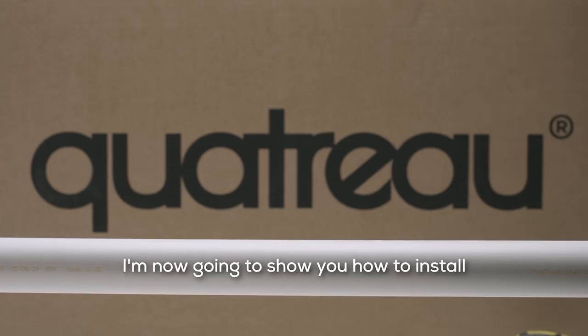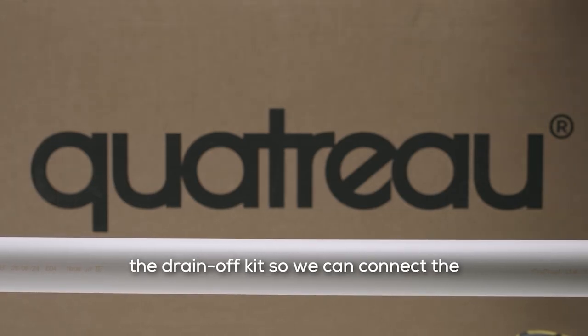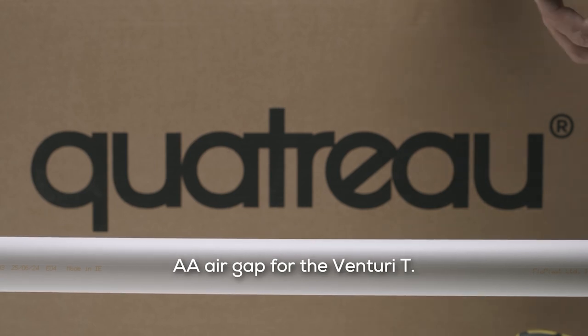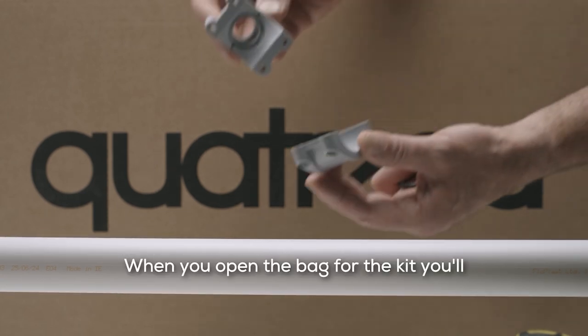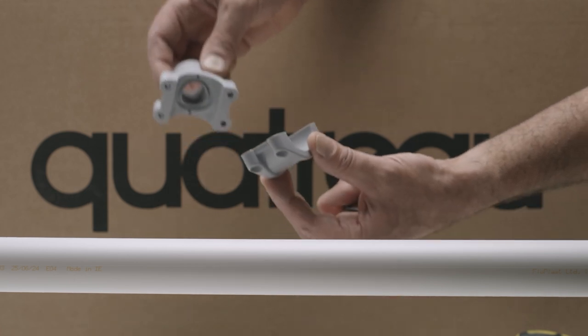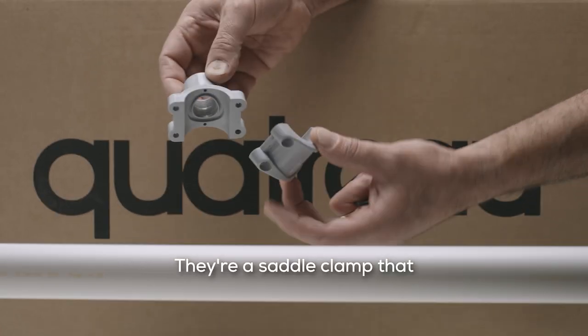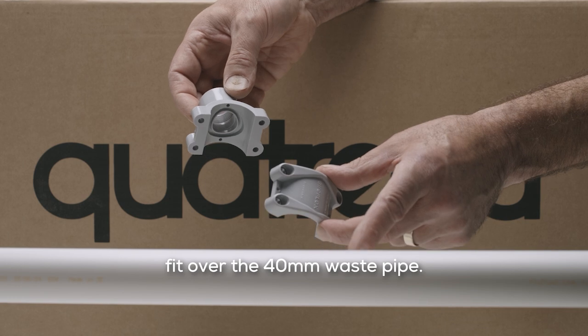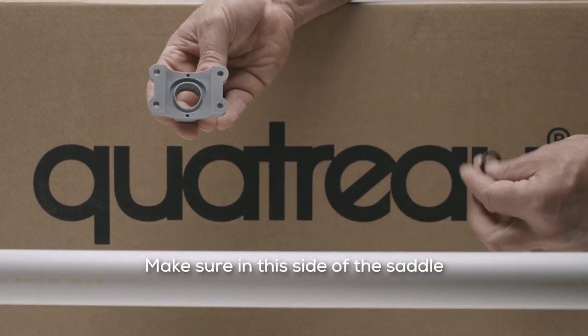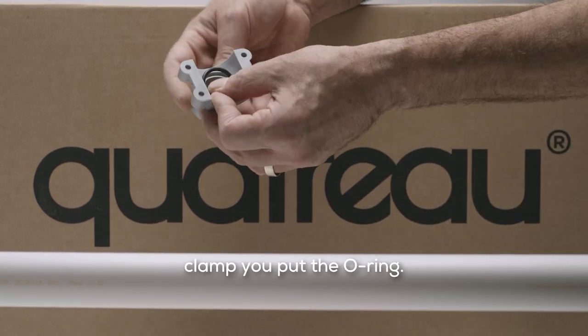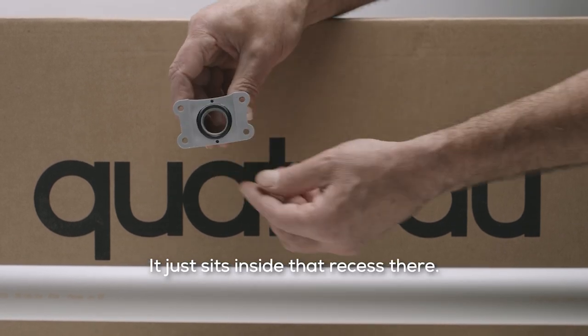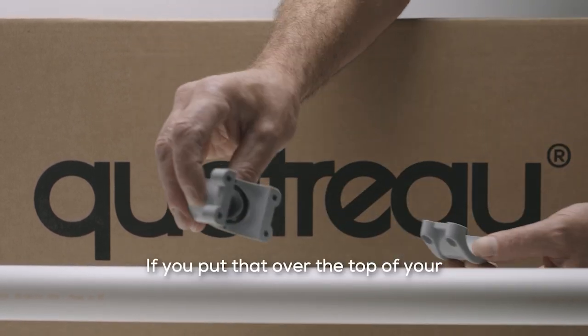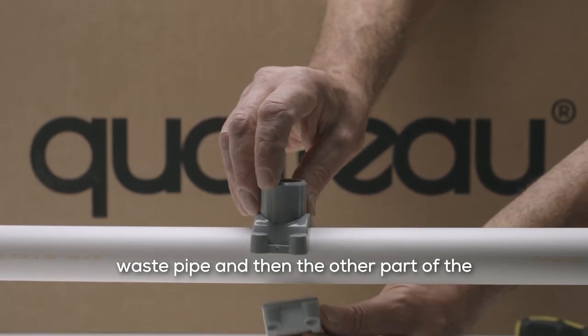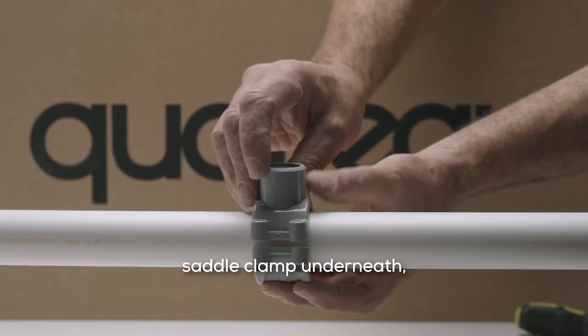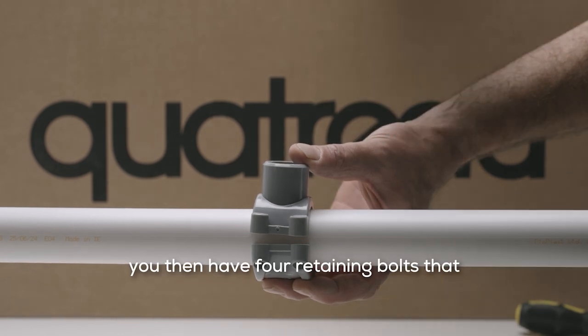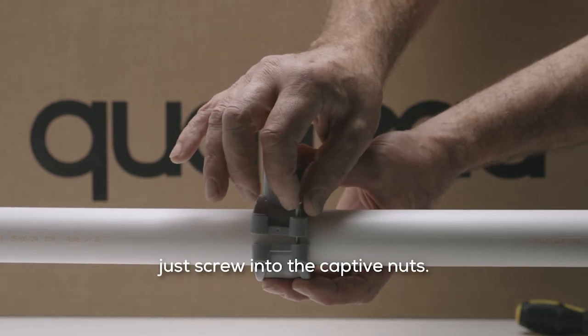I'm now going to show you how to install the drain-off kit so we can connect the air gap for the Venturi T. When you open the bag for the kit, you'll find these 2 parts here. They're a saddle clamp that fit over the 40mm waste pipe. Make sure in this side of the saddle clamp, you put the O-ring. Just sits inside that recess there. And then if you put that over the top of your waste pipe and then the other part of the saddle clamp underneath. You then have 4 retaining bolts that just screw into the captive nuts.